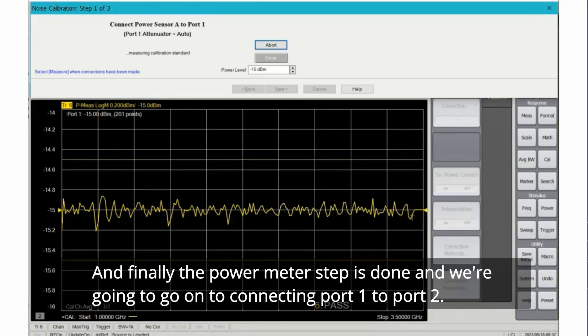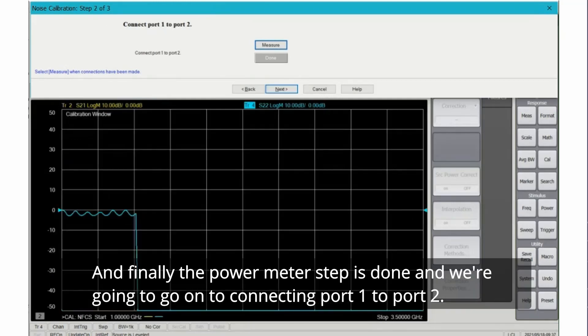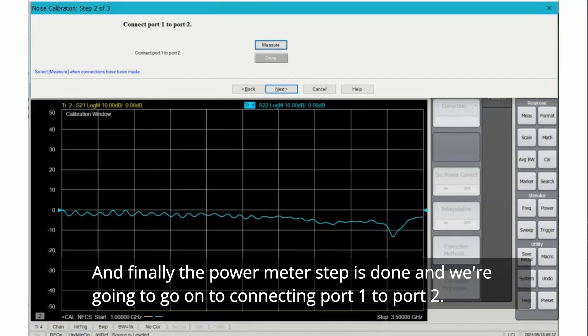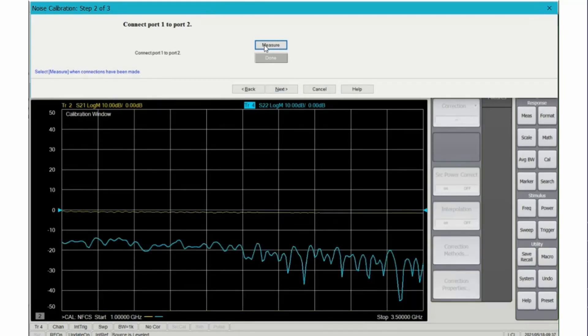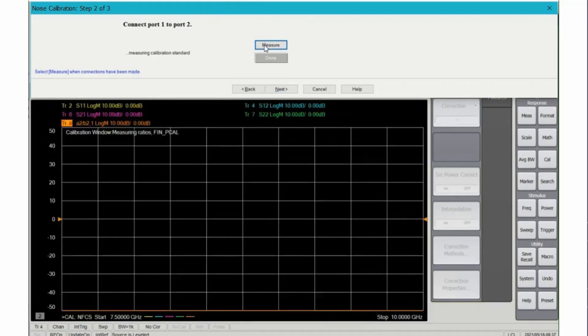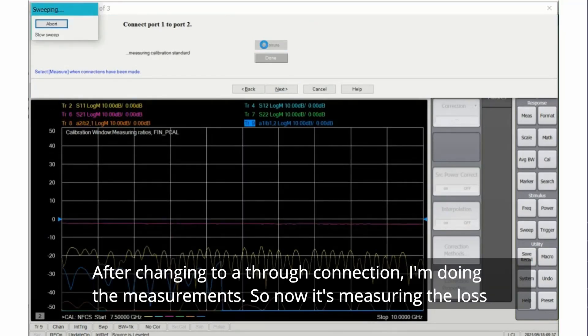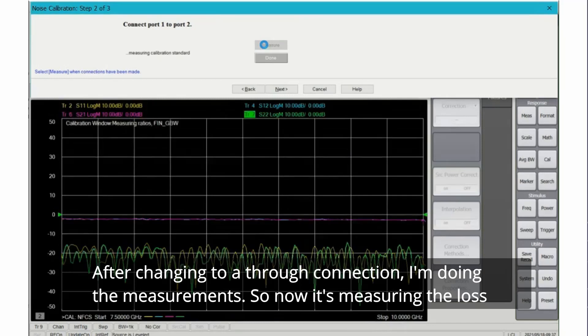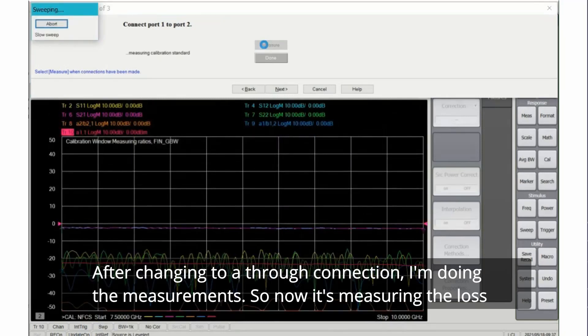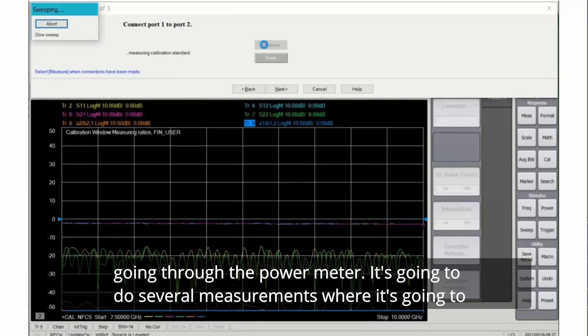And finally the power meter step is done and we're going to go on to connecting port 1 to port 2. After changing to a through connection I'm doing the measurements, so now it's measuring the loss going through the power meter.